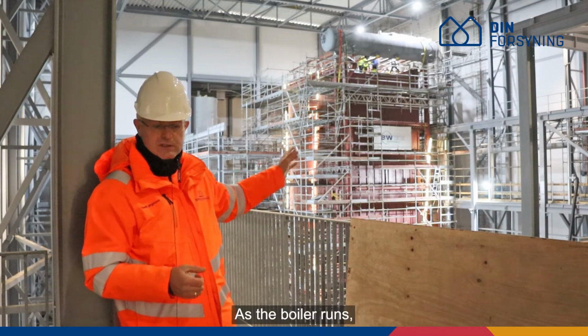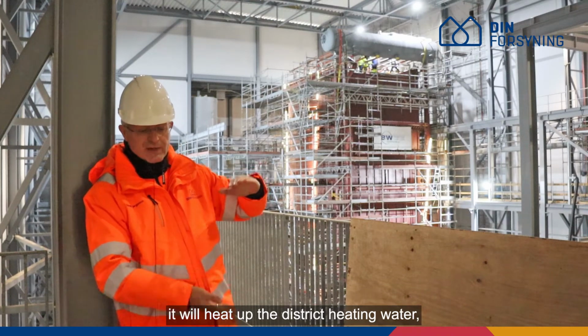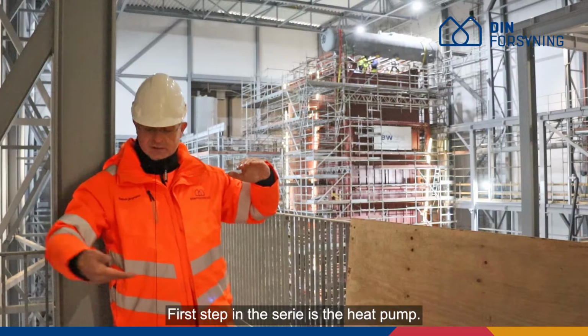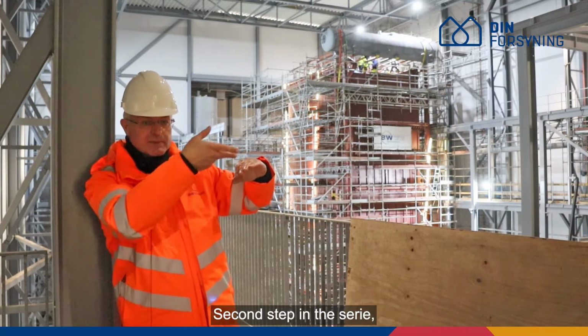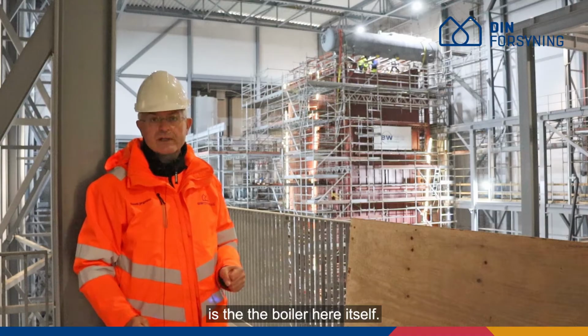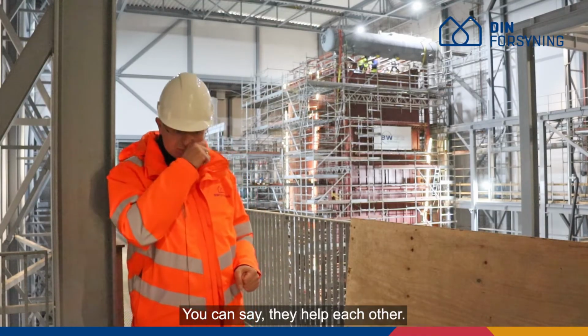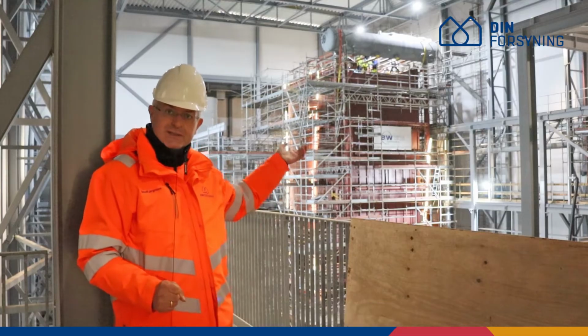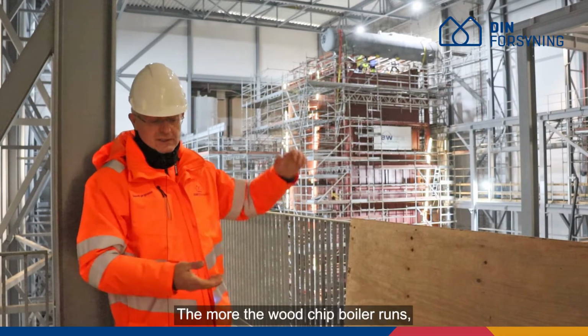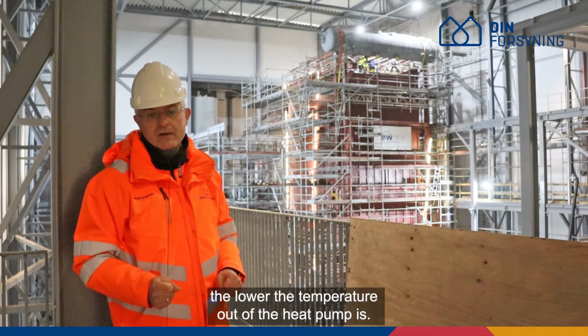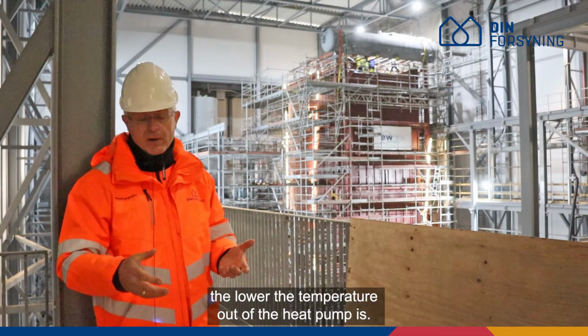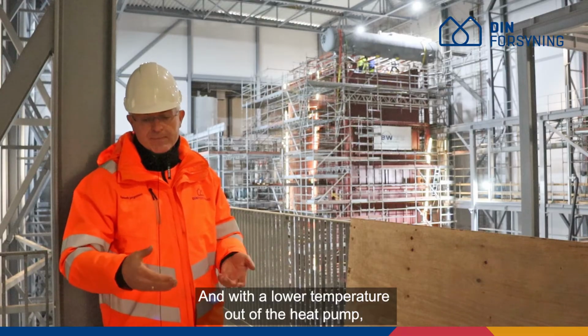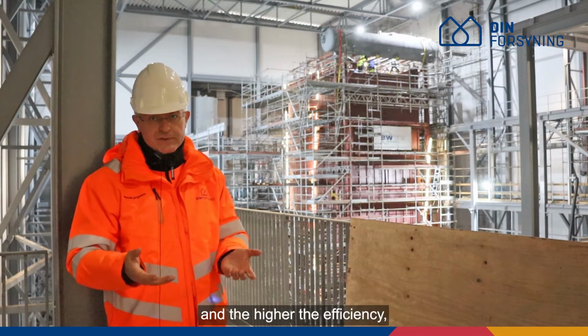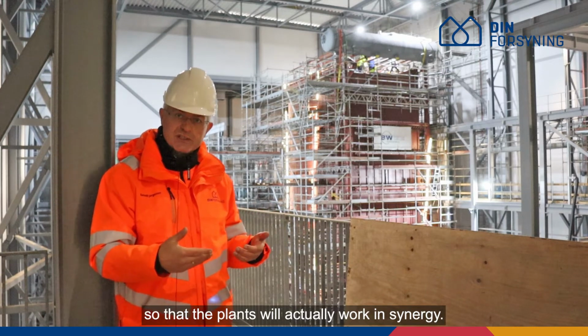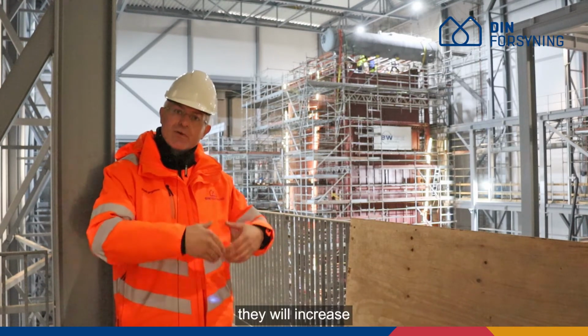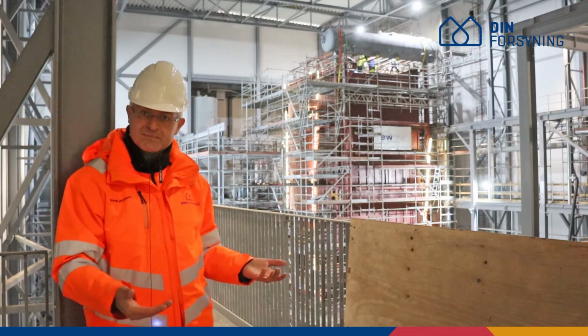As the boiler runs, it will heat up the district heating water, which goes in series. First step in series is the heat pump. Second step in the series is the boiler here itself. So you can say they help each other. The more the wood chip boiler runs, the lower the temperature out of the heat pump is, and with a lower temperature out of the heat pump, the higher the COP, the higher the efficiency, so that the plants will actually work in synergy. So when they both are operating, they will increase the efficiency on both systems.